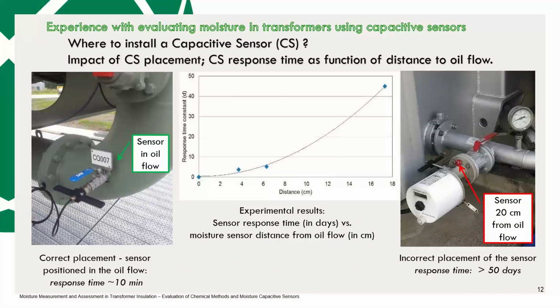Another very important point when we talk about capacitive sensors is where to install them. This is a crucial point because a capacitive sensor can deliver really reliable results only when it is in an oil flow. We can see on the left side installation in a cooler, which is a good installation because you have always moving oil there. And even at such an installation, you have a certain response time, which is about 10 minutes. It depends also on the type of sensor.